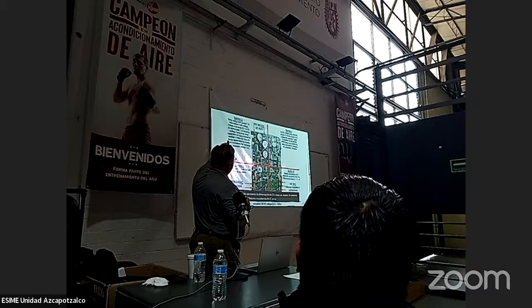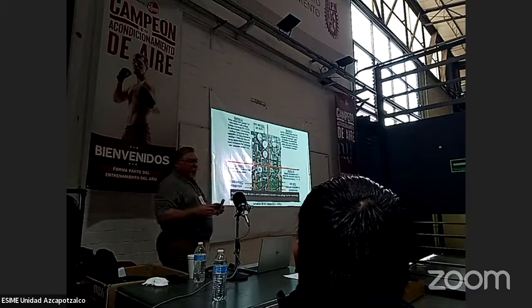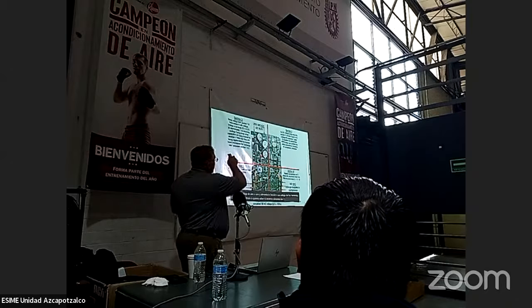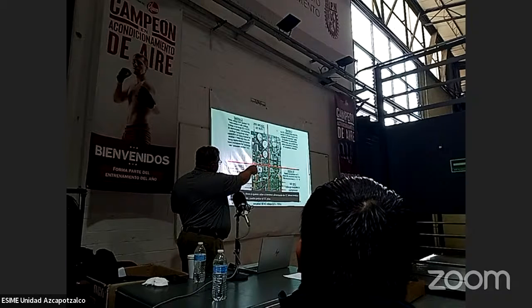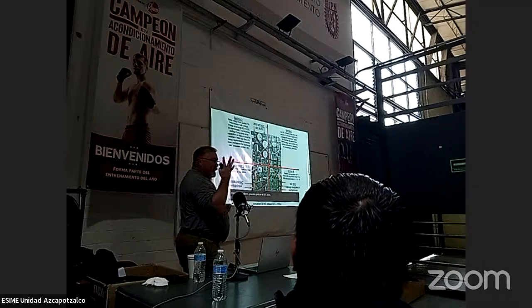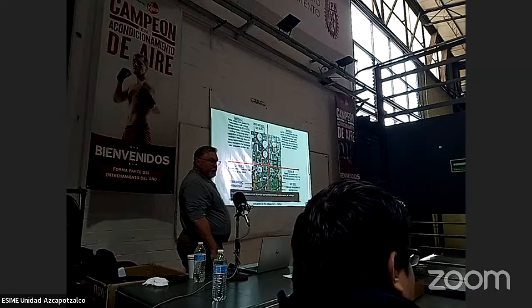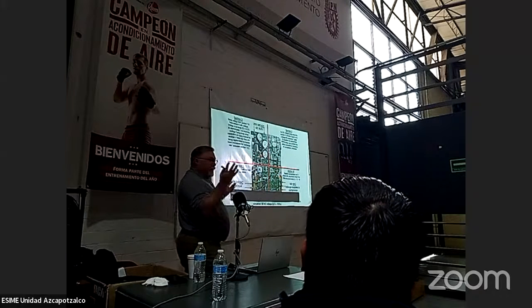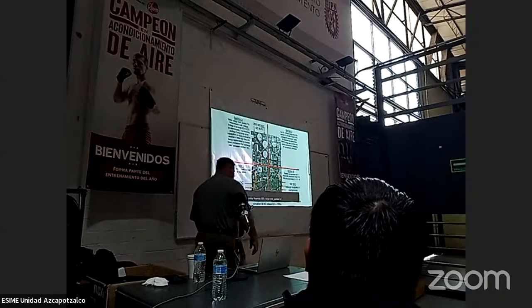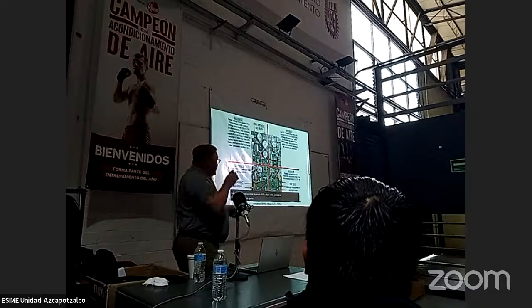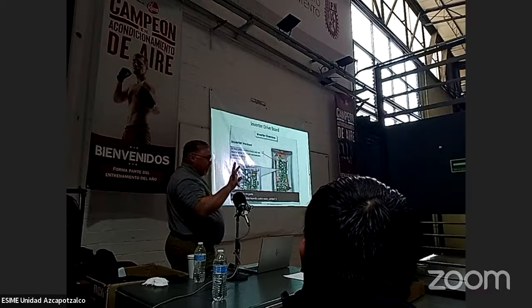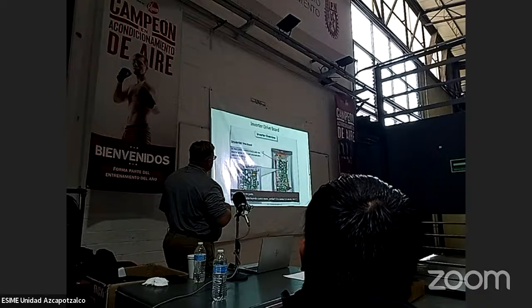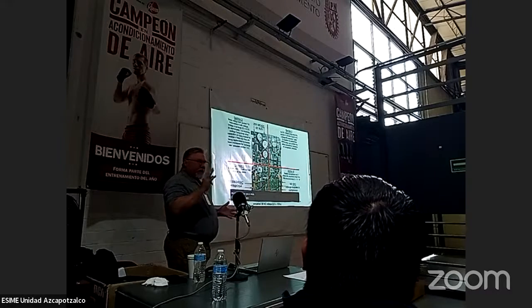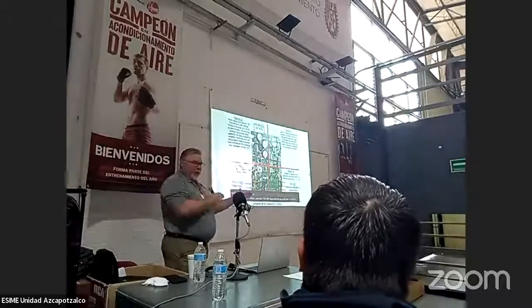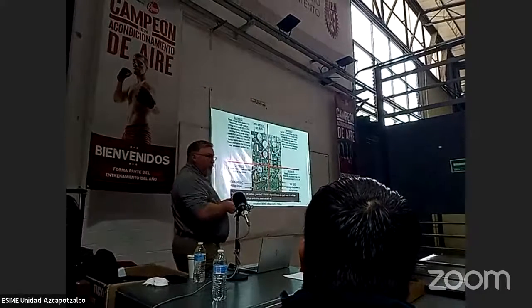Now, it stores the voltage and you can read it in section 4 with voltage from the terminals DC plus and DC minus. If you want to know if we have DC power stored in those capacitors, you can test DC plus to DC minus, and you should be reading about 4 times the incoming voltage. So with 220, you should be reading 300 and something volts. Or, I'm sorry, 1.4 times, not 4 times, 1.4 times. So a little over 300 volts, 360, 380, depending on what the voltage is. It will vary based on your incoming voltage, but it will be roughly 1.4 times the incoming voltage in DC.